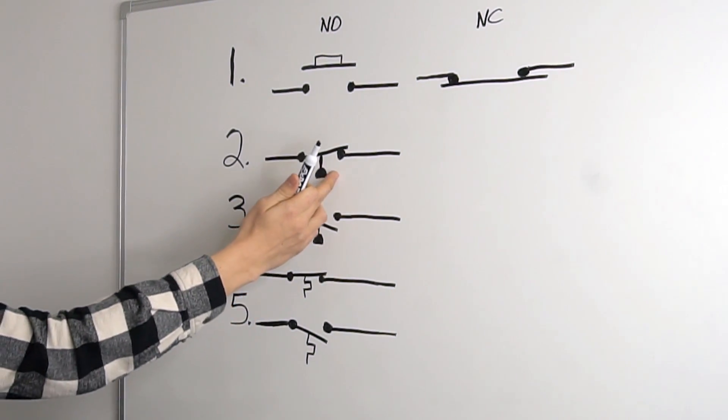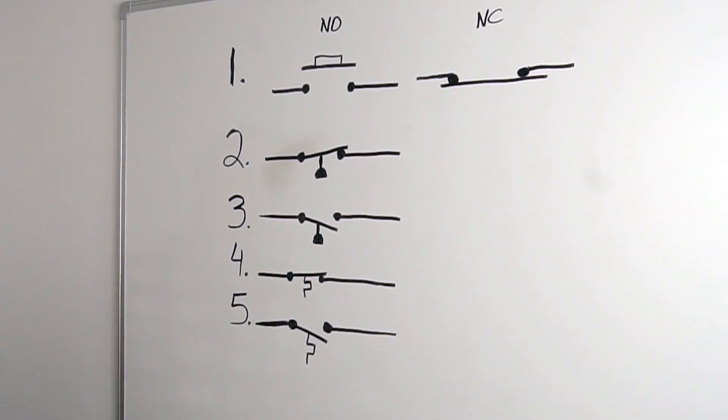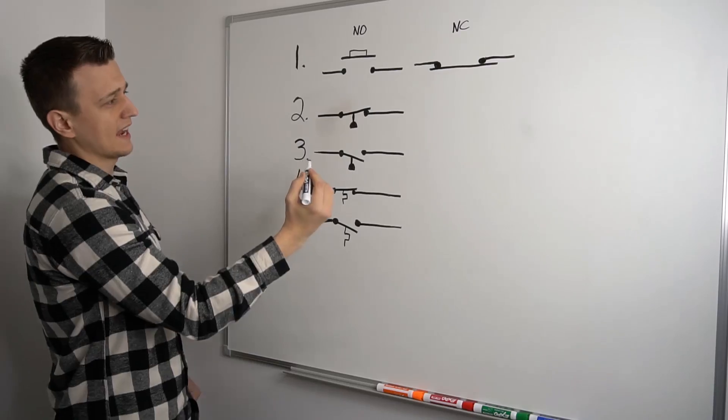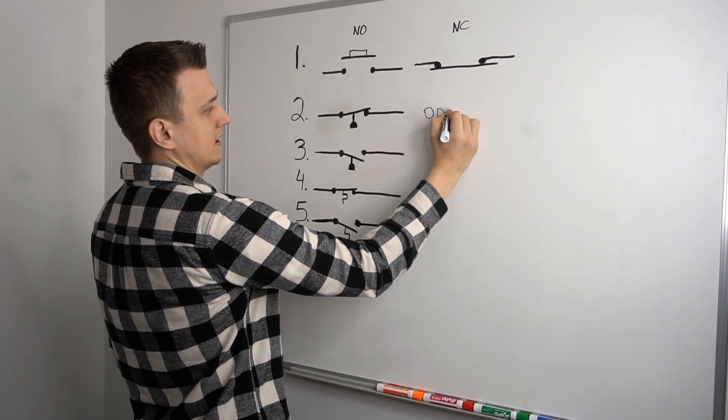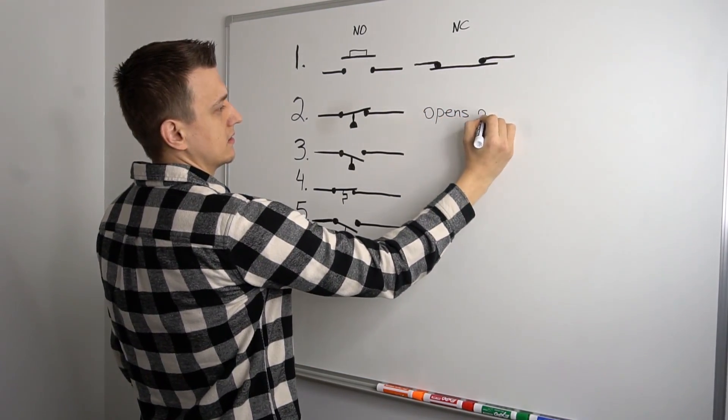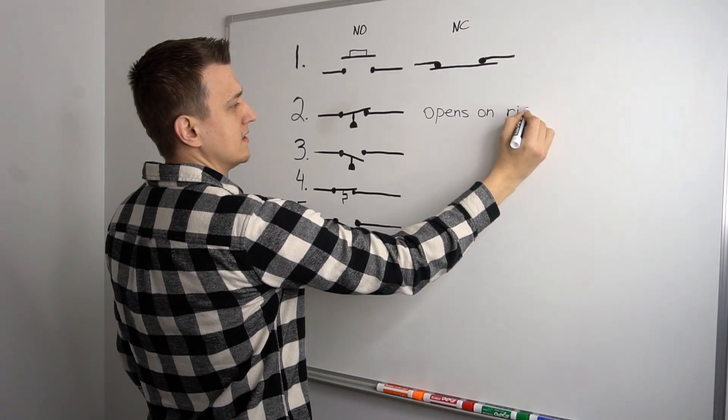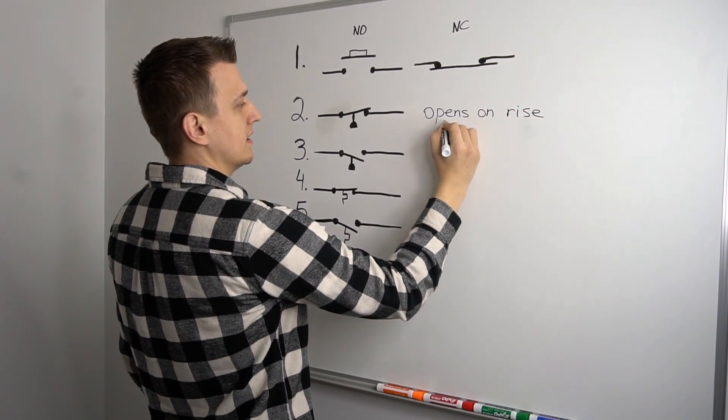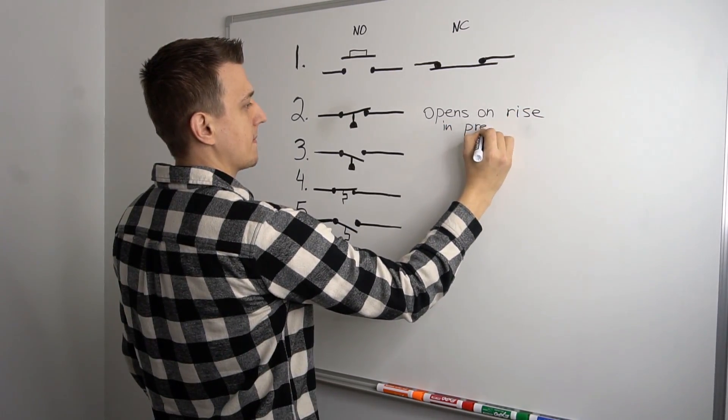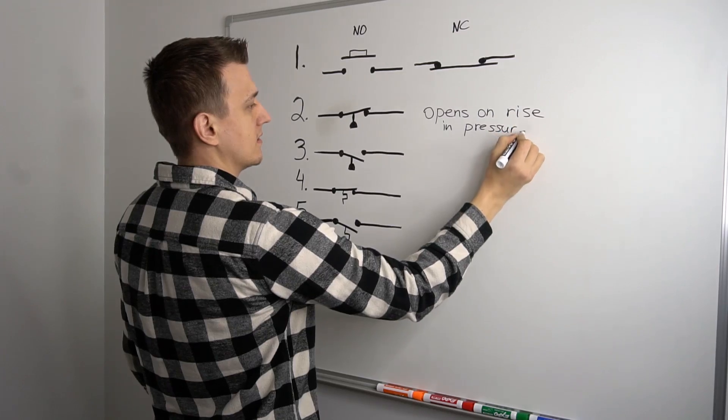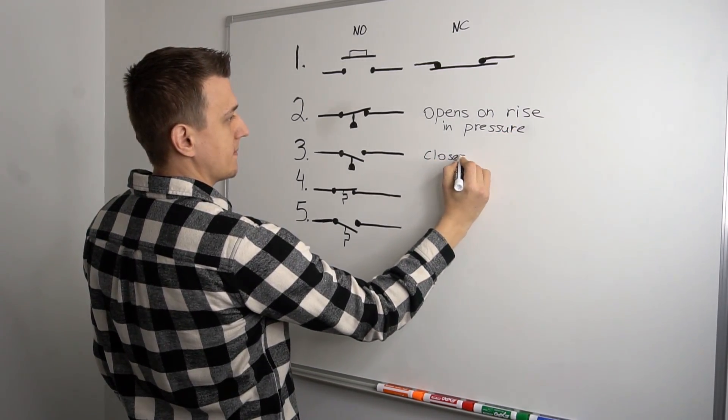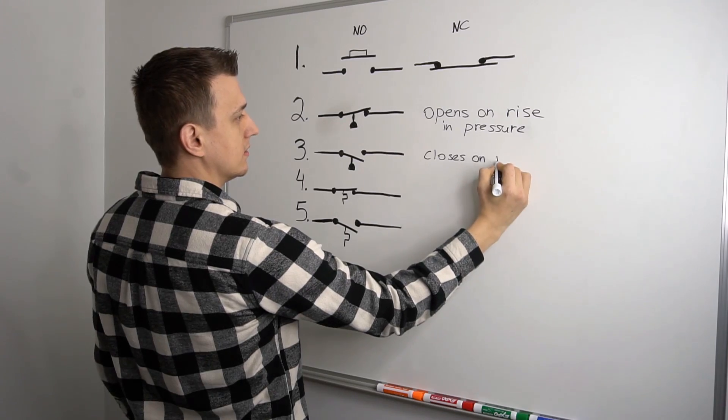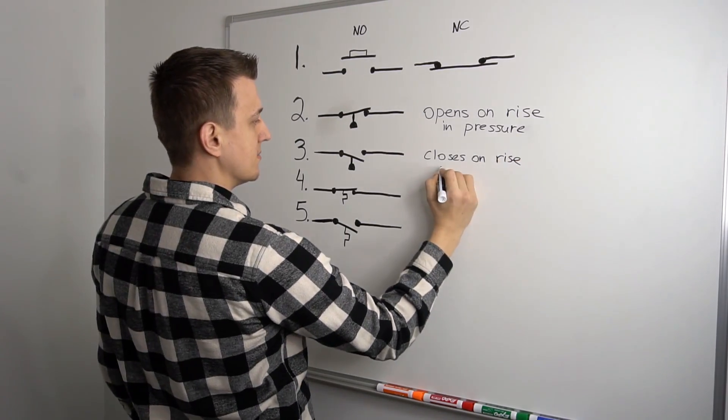These pressure switches, they basically either close on the rise of pressure or they open on a rise of pressure. So this one right here is a normally closed pressure switch. This one is a normally open pressure switch. And actually, let's go ahead and write that down. So this one opens on rise in pressure.